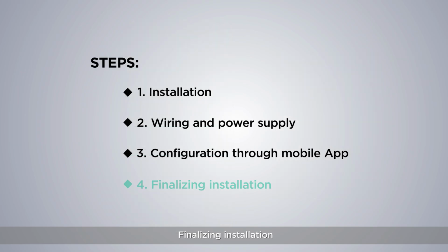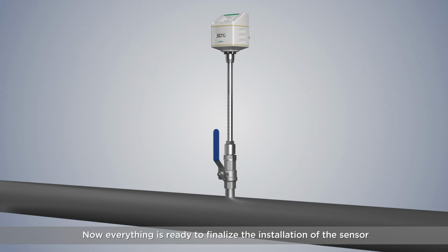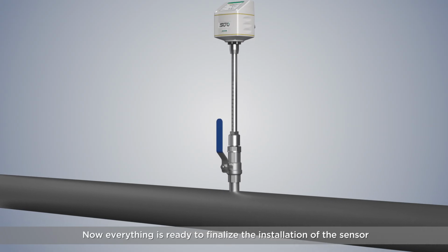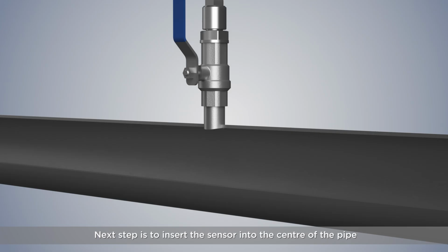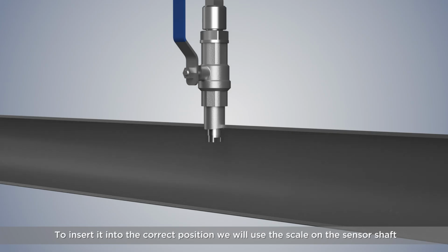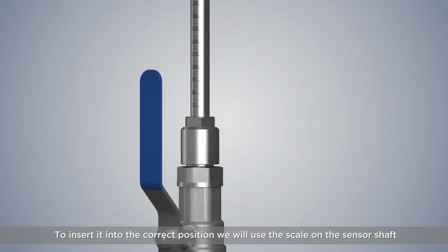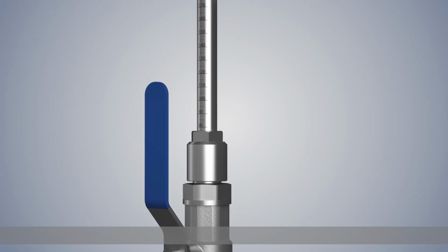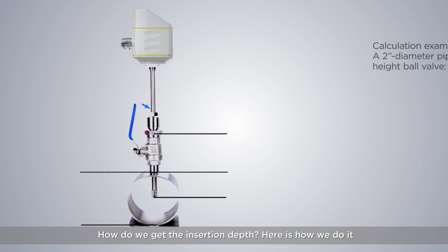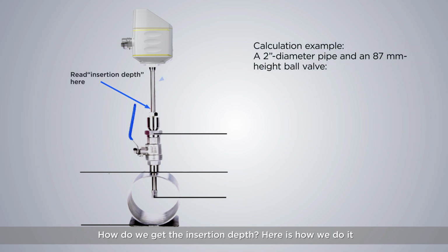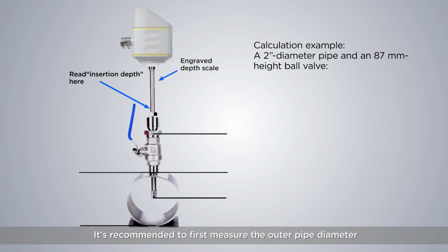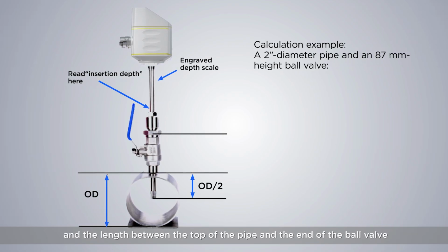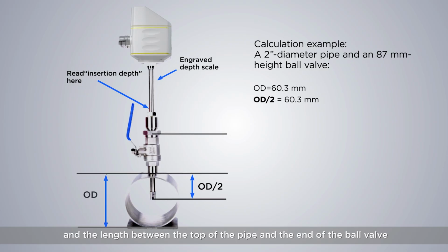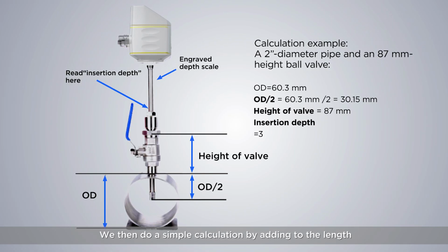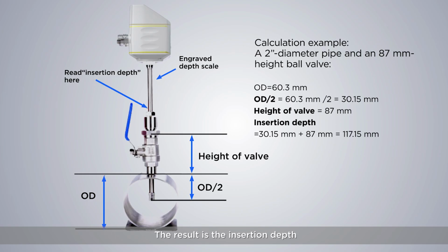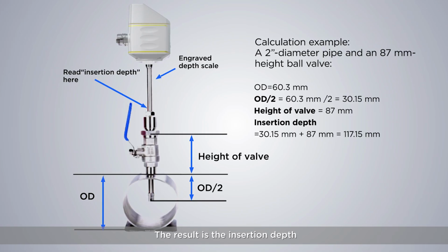Finalizing installation. Now everything is ready to finalize the installation of the sensor. The next step is to insert the sensor into the center of the pipe. To insert it into the correct position, we will use the scale on the sensor shaft. How do we get the insertion depth? Here's how we do it. It's recommended to first measure the outer pipe diameter and the length between the top of the pipe and the end of the ball valve. We then do a simple calculation by adding to the length measured half of the outer diameter. The result is the insertion depth.